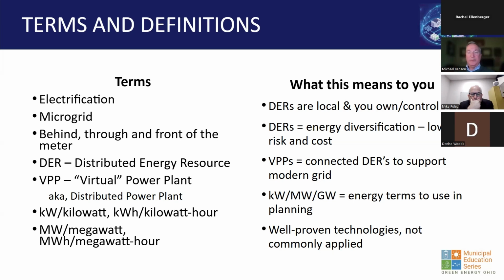For example, if you have electric police cars, ambulances, and fire trucks in the future, you're going to need megawatt charging, which is what the over-the-road trucking industry is moving to now. Megawatt charging is 480 volts, but now we're talking 1,250 amps to get to 600 kilowatts, or 800 volts at 1,250 amps to get to 1 megawatt.